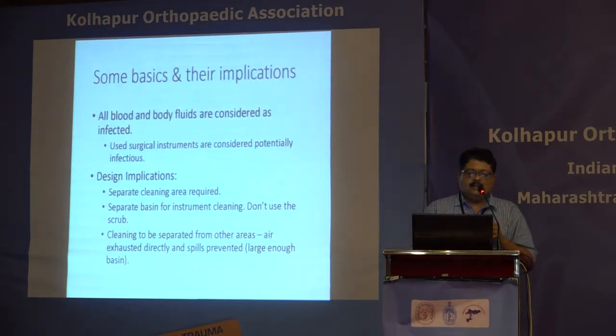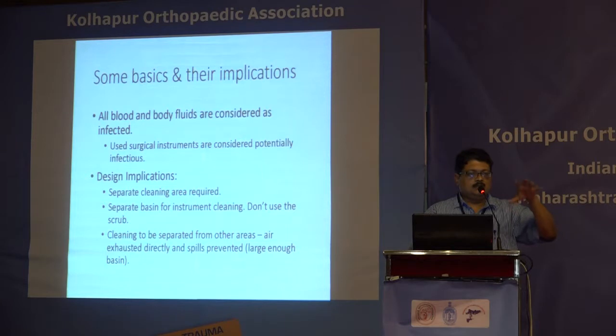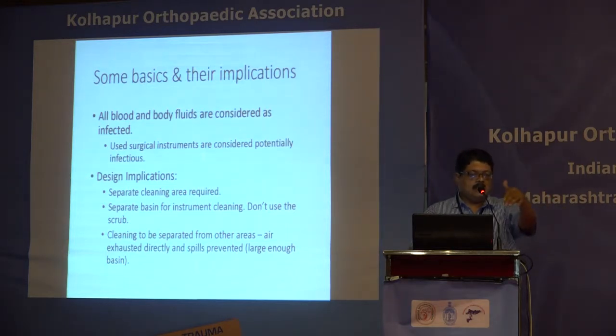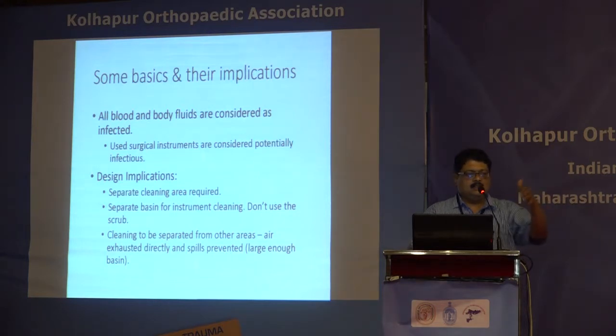There should be a cleaning area separate from other areas where drums are packed and the autoclave is kept. Even in the CSSD room, even if you have one single room, make sure there's a separate basin and if possible it is partitioned off from the rest of the room. This segregation of clean and dirty needs to be maintained.